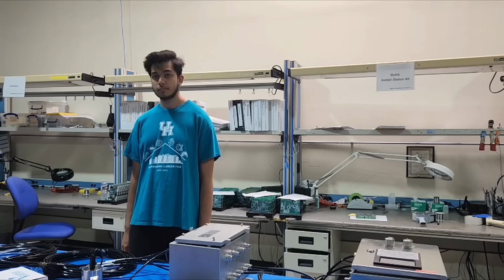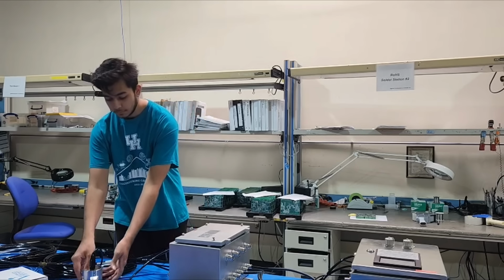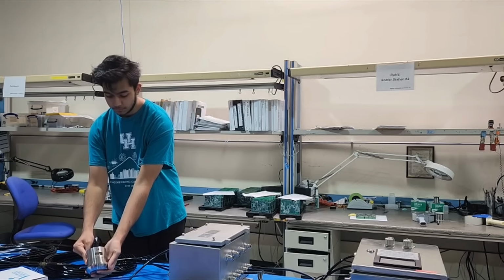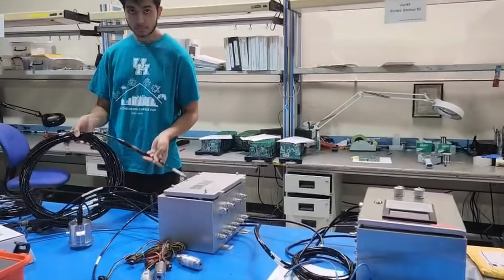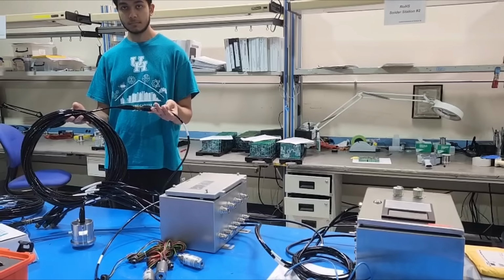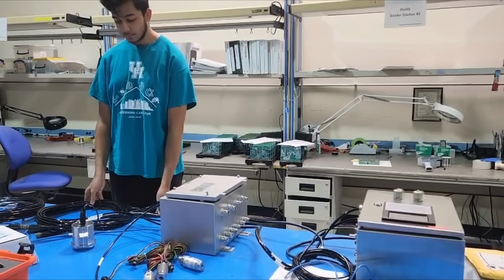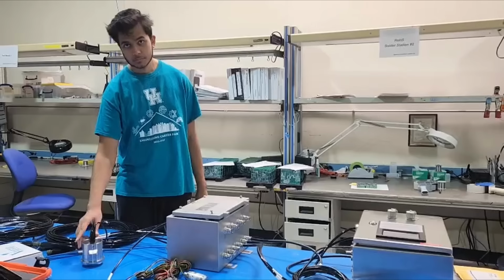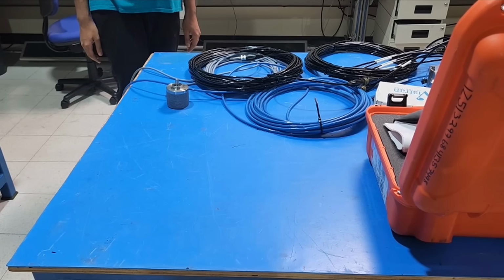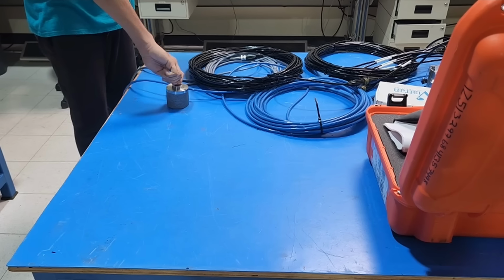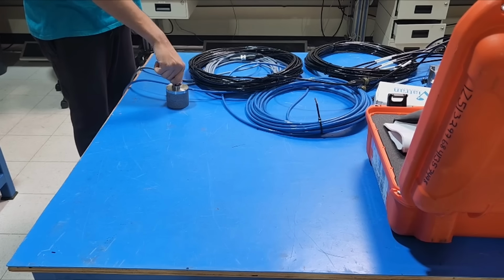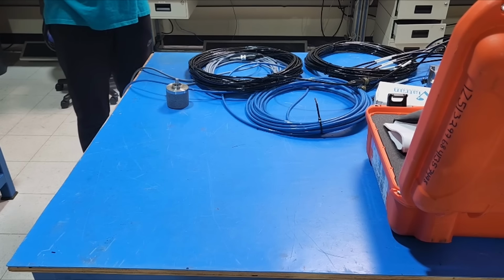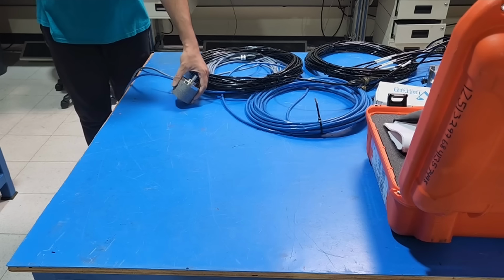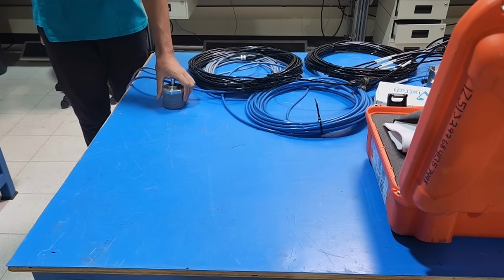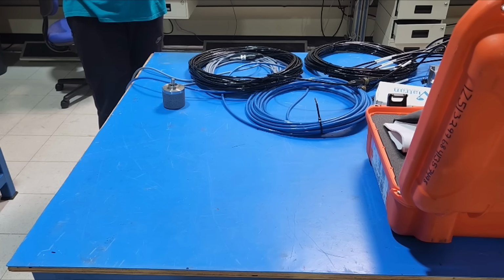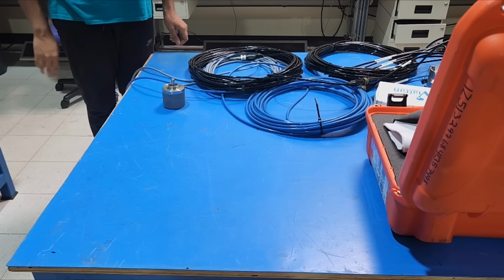Next, we will go over the sensors on the rig kit. Here we have a 1502 Union pressure sensor rated for 15,000 psi, connected to the RapidLogger barrier box with a standpipe pressure cable. Another 1502 pressure sensor is connected to the wellhead or annulus pressure cable. The encoder is connected to the rig winch shaft on a drilling rig or to a pulley system on a hydraulic jack rig where there is no winch. The purpose of the encoder is to measure the block position or the height of the jack cylinders. This information is used to calculate the pipe depth in the RapidLogger software.